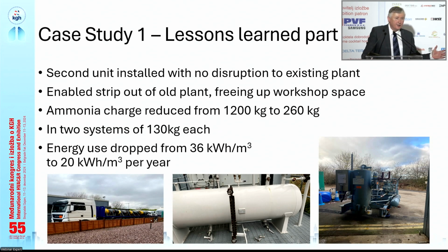That allowed us to decant all of the ammonia from the old plant, which was about 1,200 kilograms. And you can see all the barrels arriving on the left-hand side in the truck to take away the recovered ammonia. Each of the new units has a 130 kilogram charge, so we dropped the total charge from 1,200 kilograms to 2 times 130. And the energy use dropped from 36 kilowatt hours per cubic meter to 20 kilowatt hours per cubic meter, so just about half of the consumption previous.